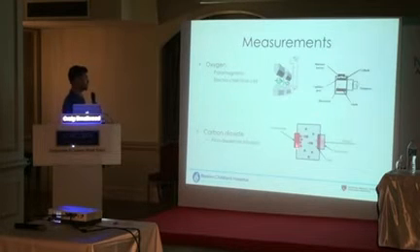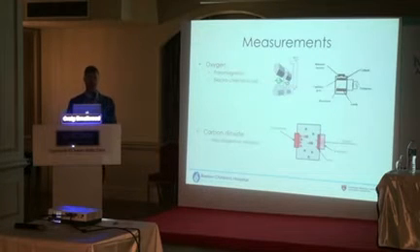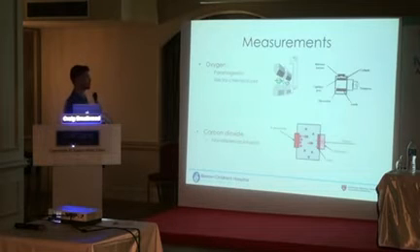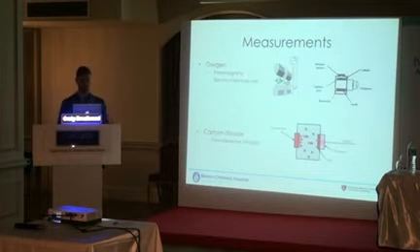So what this thing does is, this is our breathing circuit, this little gray box, and these little black dots are the carbon dioxide molecules. And there's an infrared photodiode, so just a little infrared light source here. Then it's going to shine this across this source, and then we're going to measure it on the other side. And carbon dioxide as a gas absorbs that light and starts to vibrate a little bit. But basically you get a discrepancy, so you have a set amount of light that is shone from this side, and then you measure how much came out that other side, and the discrepancy between those two is the CO2 concentration.